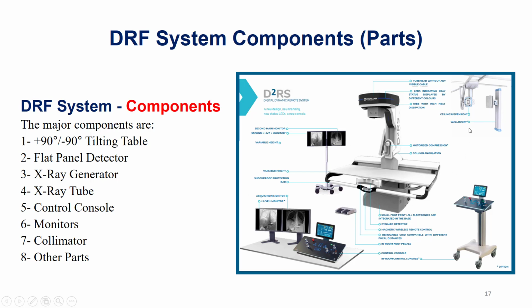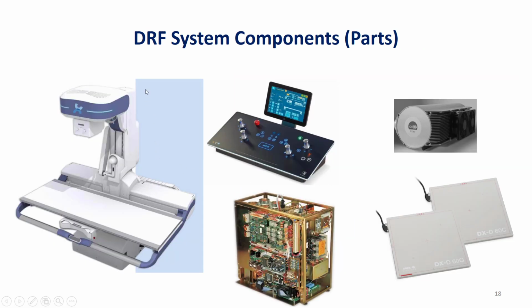The photo on the left is for a typical flat panel DRF system with its major components and parts. In this slide we can see the photos of major DRF system components or parts. The first image is for the tilting table with plus 90 degree tilting angle and minus 90 degree tilting angle. You can also see the operator control console. Another component is the X-ray generator. Also we can see here the image or photo for an X-ray tube. And finally we can see the image for the dynamic flat panel detector.